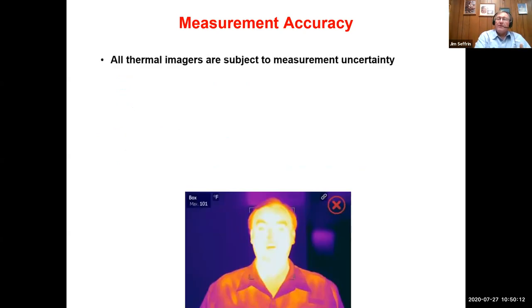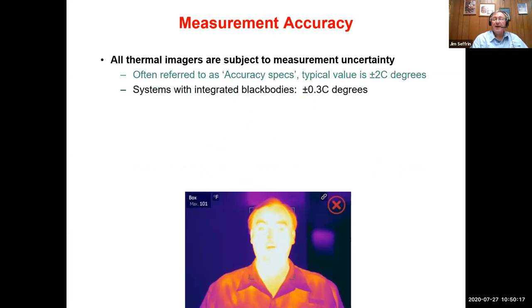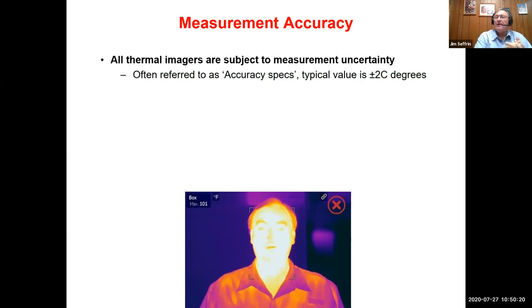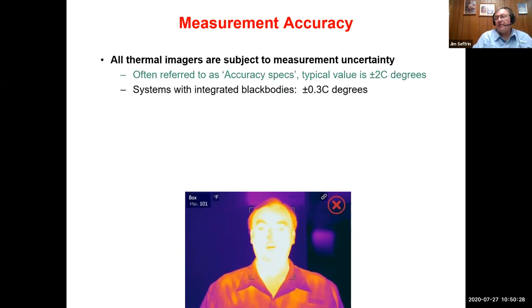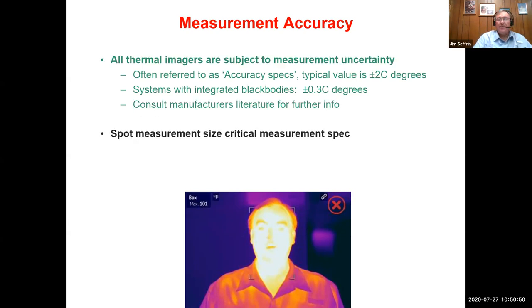Be aware that all thermal imagers are subject to measurement uncertainty. These are often referred to as accuracy specifications. A typical value is within, or you can also read that as plus or minus, 2 Celsius degrees or 3.6 Fahrenheit degrees. Systems that have integrated black bodies, these are dedicated, very expensive systems ranging anywhere from around $8,000 and up, although there are some cheaper than that, are typically within 0.3 C degrees. They're designed to be highly stable and accurate. In order to understand more about measurement uncertainty, consult the manufacturer's literature for further information.